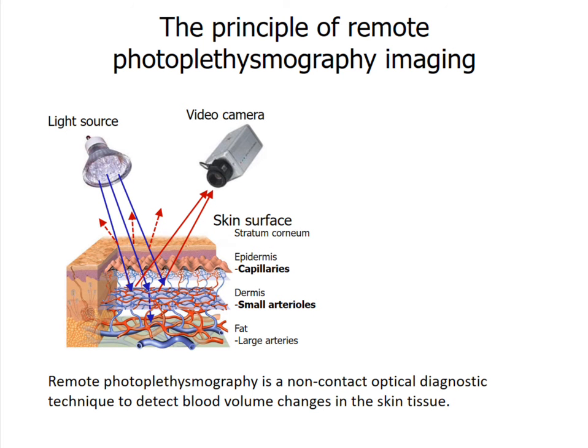First of all, I would like to explain the principle of remote photoplethysmography technique. Remote photoplethysmography is a non-contact optical diagnostic technique to detect blood volume changes in the skin tissue. The rPPG technique requires a visible or near-infrared light source and video camera. Light penetrates into the skin, where it reaches small blood vessels and is partly absorbed in the blood. Due to cardiac activity, blood volume changes, and this leads to modulation of light intensity in skin tissue. A video camera is able to detect small intensity variations of backscattered illumination.